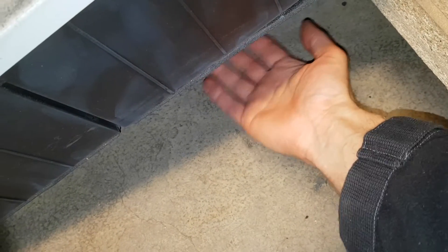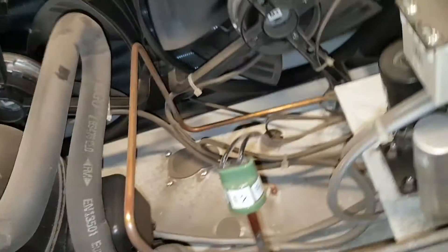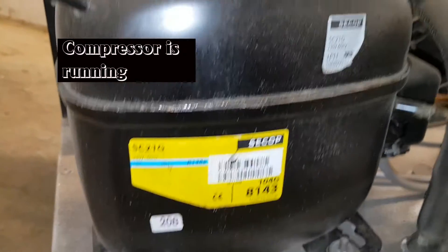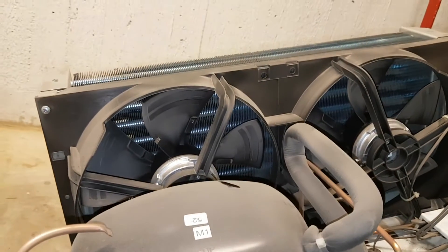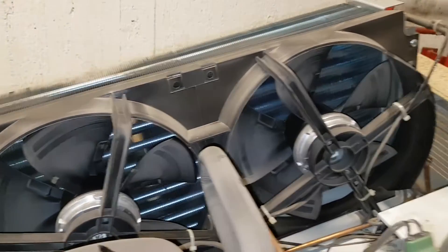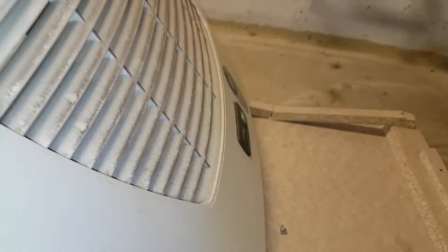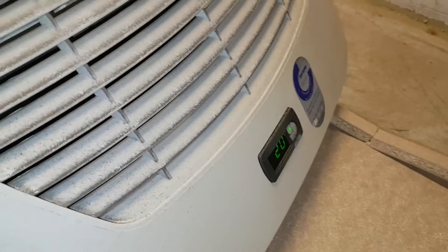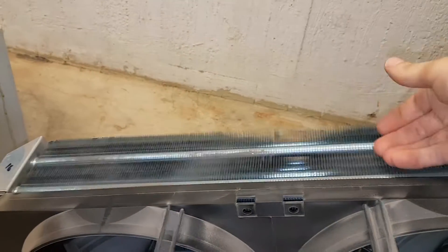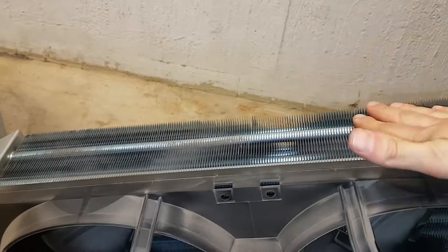You can feel the temperature coming from here. This is the compressor - it used to be a Danfoss, now it's a Secop. I'm just checking out and trying to find what's not working. This is hot - yeah, this is too hot. It's not being cooled down.